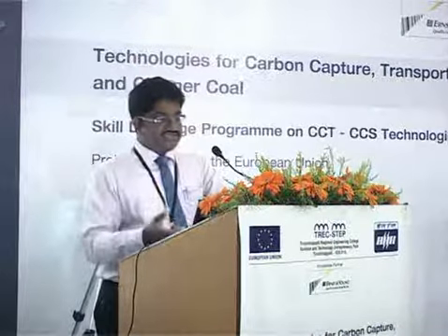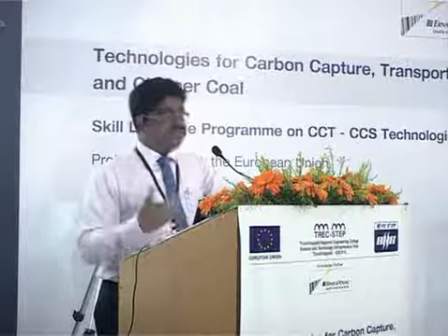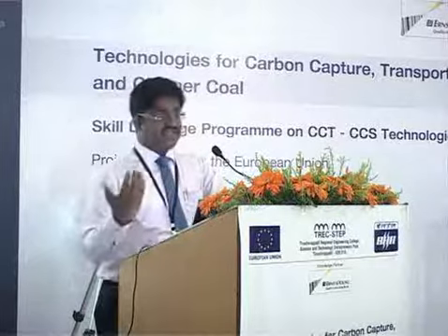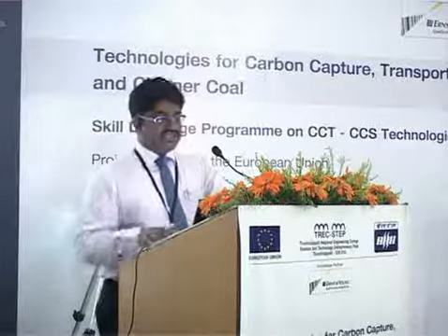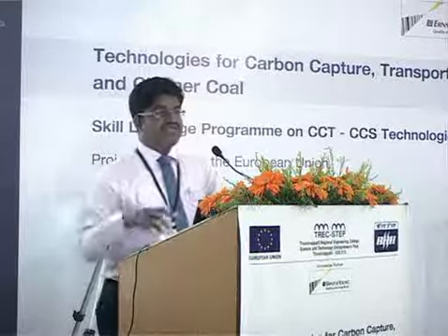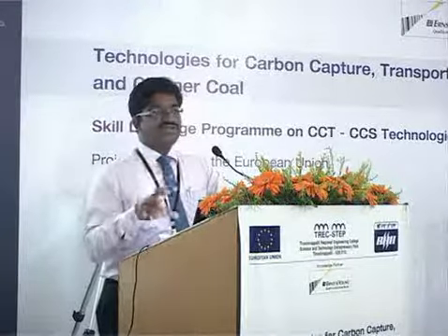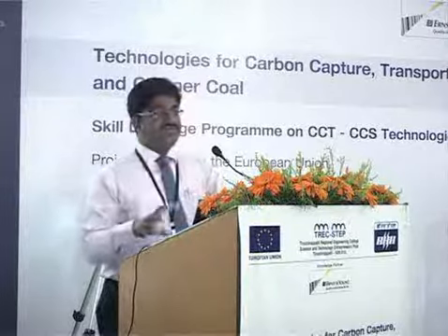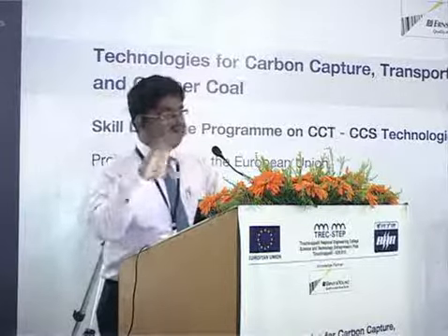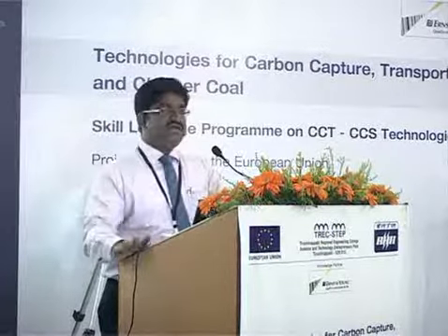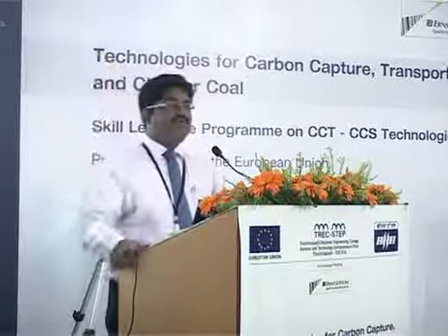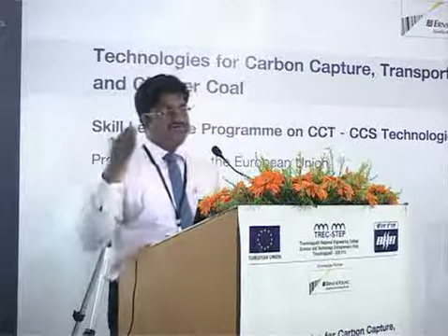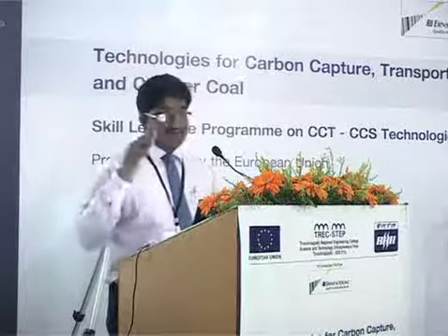So what they did, they just did some retrofit. They have changed some rotors, blades, and diaphragm sets. So these are some of the 4 or 5 parameters which they changed. I just want to give some examples, because whenever you come across these types of projects, like a turbine retrofit, normally people will think that CDM is applicable only for renewable energy plants. But no, it's applicable for energy efficiency projects, and primarily for power plants.